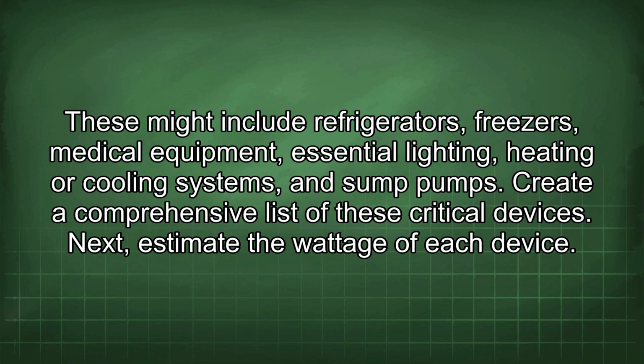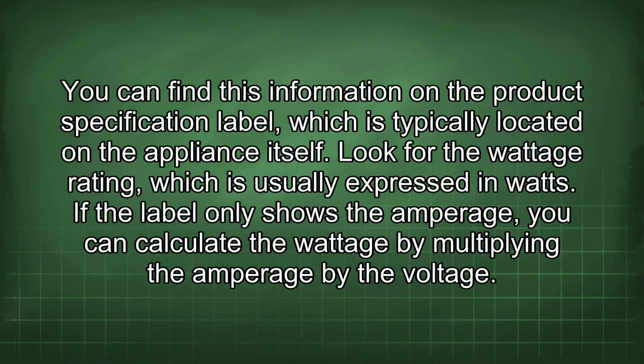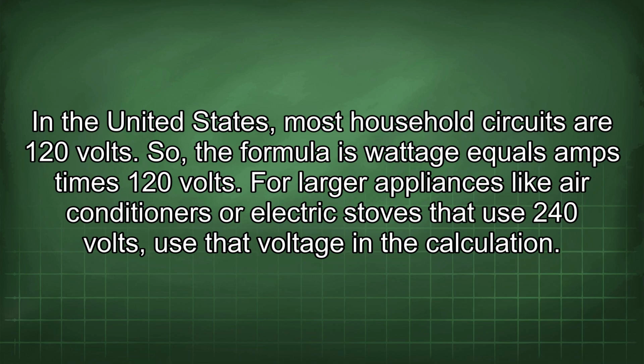Next, estimate the wattage of each device. You can find this information on the product specification label, which is typically located on the appliance itself. Look for the wattage rating, which is usually expressed in watts. If the label only shows the amperage, you can calculate the wattage by multiplying the amperage by the voltage. In the United States, most household circuits are 120 volts. So, the formula is wattage equals amps times 120 volts. For larger appliances like air conditioners or electric stoves that use 240 volts, use that voltage in the calculation.